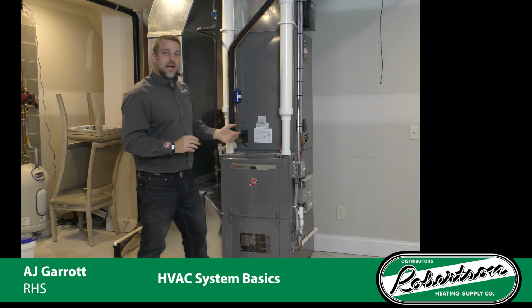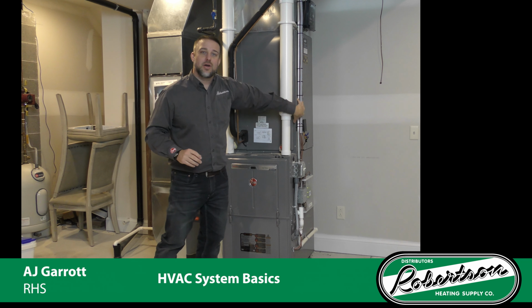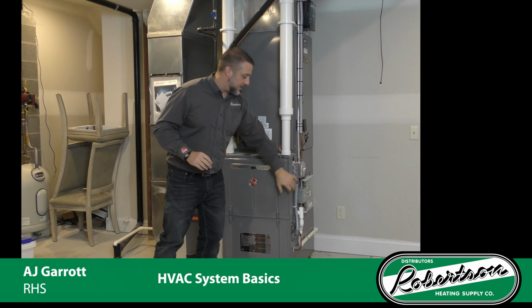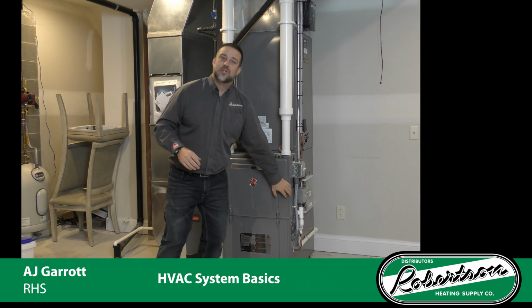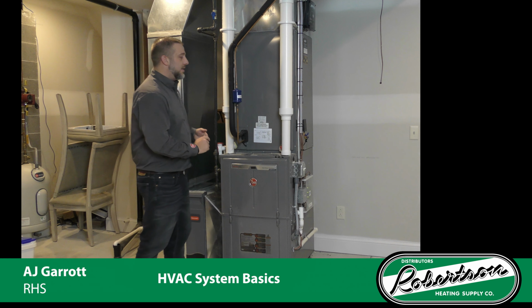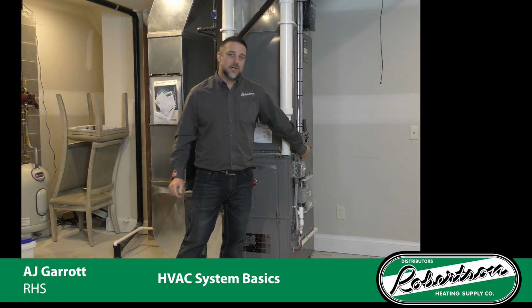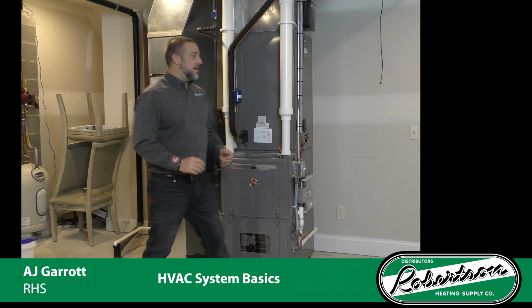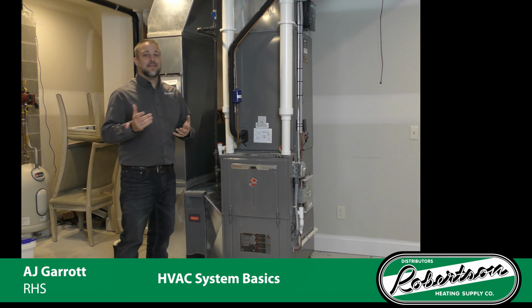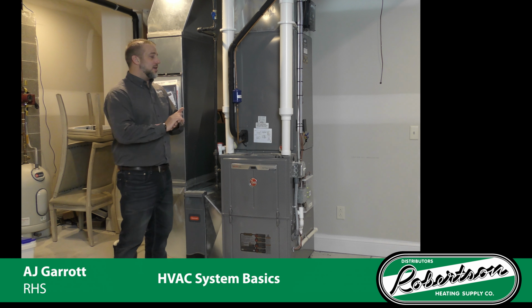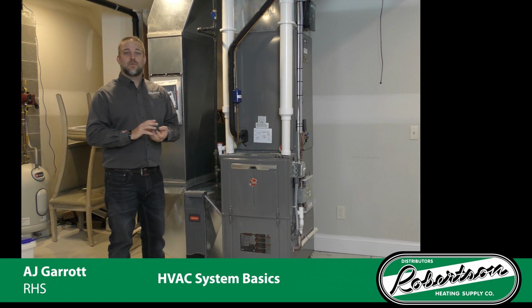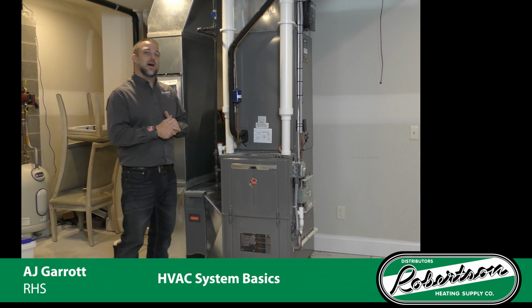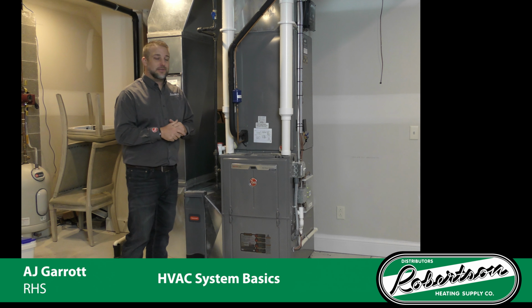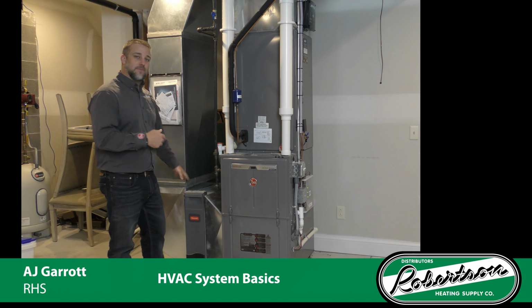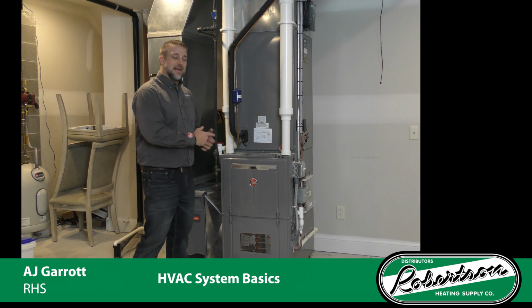The electrical side of this, we're bringing 110 volt electric down the furnace and into the control box or into a switch for safety. And then we also use thermostat wire, which comes down. Thermostat wire is typically 18 gauge. It could be anywhere from 2 conductor or 5 or 8 conductor, depending on the application that you have. We'll break into the filter here in a minute, and same with the gas furnace.